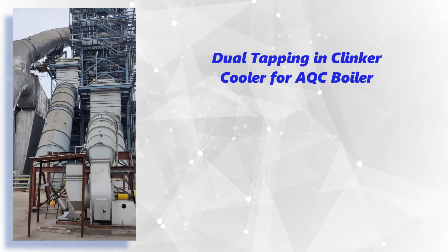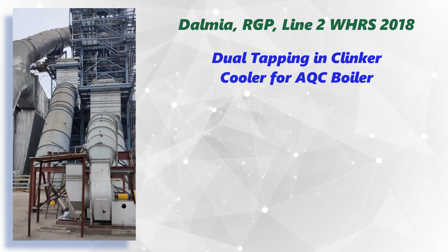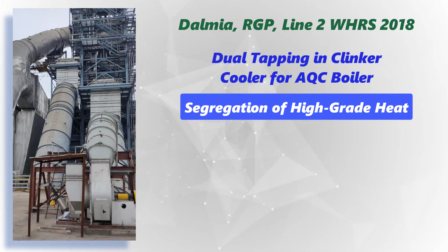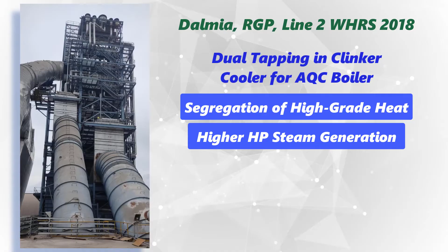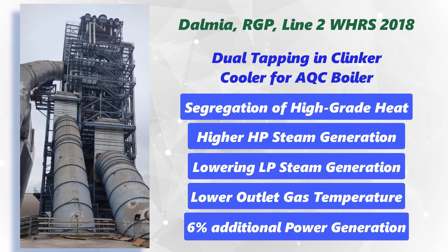He conceived the concept of dual tapping in the clinker cooler for the AQC boiler in the WHRS project at Dalmia RGP Line 2 in 2018. Major benefits of this concept include segregation of high-grade heat to generate higher steam temperature, higher HP steam generation with respect to LP generation, which helps enhance power generation, lowering LP steam generation, and reduced loading on the condenser. A lower WHRS outlet gas temperature can be achieved, resulting in a gain of about 6% in gross power generation.